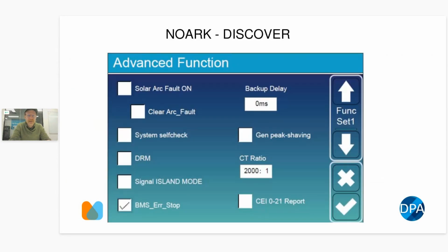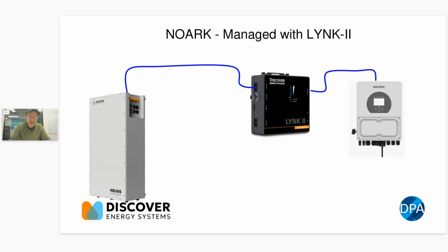The other thing I'll say about Noarks is most of the tech calls I have for Noark are one of two things. It's DRM, demand response mode. It comes with that default switch to be on, and you don't need it other than in Queensland for a certain DNSP. Everyone else doesn't use it, so you just turn that off. The inverter just won't turn on if you don't have that switched off. And the other thing is that there's an on button on the side of the inverter, and it's counterintuitive because the LCD display is on whether you've got the on button on or off. So you think that you've got the inverter on because the LCD display is lit up, but actually you need to press the silver button on the side.